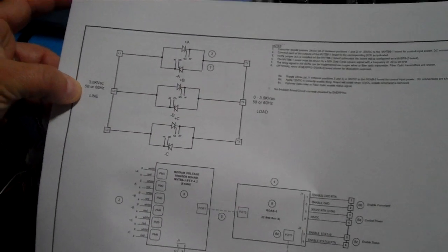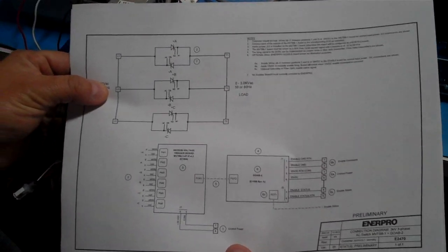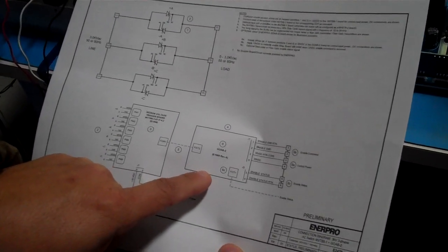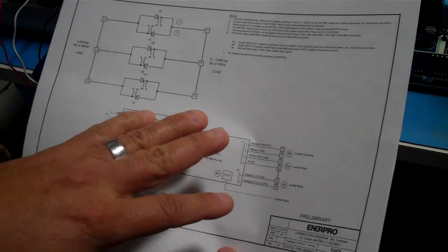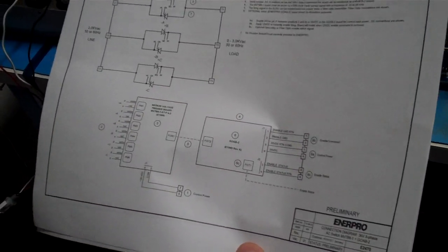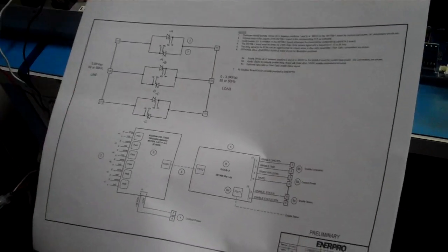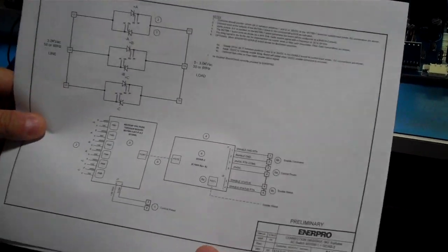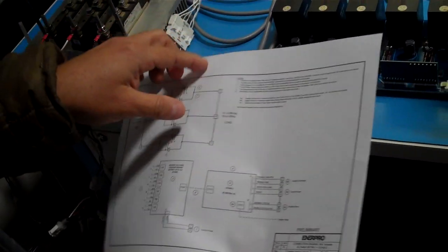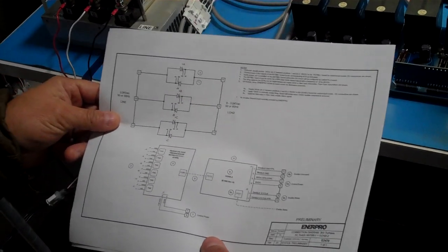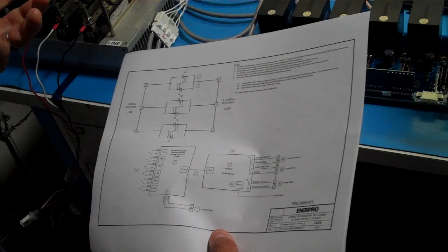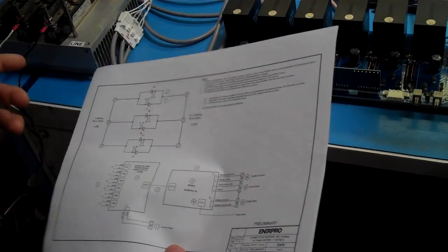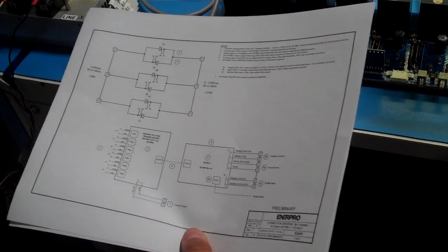We are using 480 on this video, just for illustration purposes, and we'll show that the GOAB board, which is the board that generates that firing signal. By the way, the GOAB board right now is configured so that when 12 volts is applied, we fire a signal. When the 12 volts is removed, it inhibits. We can always change the logic according to the corresponding schematic for that board, so that it fires when the 12 volts is removed and inhibits when it's present. And basically it's an all or nothing kind of situation.